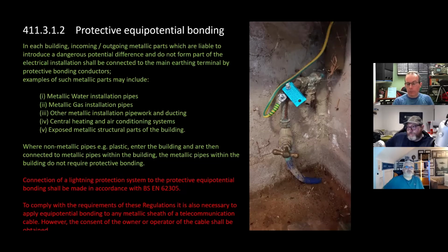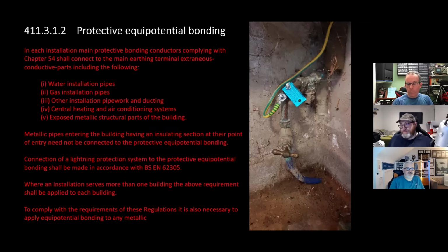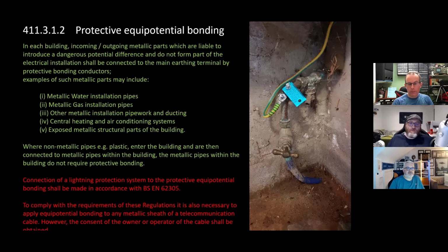What's everyone's view on that, because it's changed at the top: in each building. Incoming, outgoing - if we just flick between the two, they've added the word metallic to each of the different things, so main bonding conductors complying with... it's now in each building, incoming, outgoing metallic parts. I think the reference to building is an improvement, because you've got the situation where you've got your garden shed or workshop down the garden, and it's like, is it part of the same installation or is it separate? But now it's like, here's a building, here's a different building, therefore you're going to do it. And they've obviously added the mention of dangerous potential differences, which helps us understand more about what we're trying to achieve with bonding, because that's not there before.